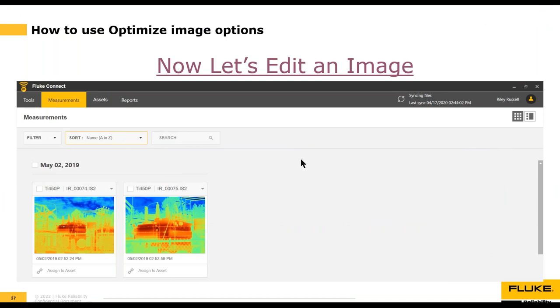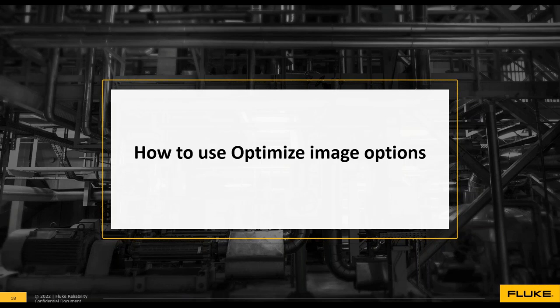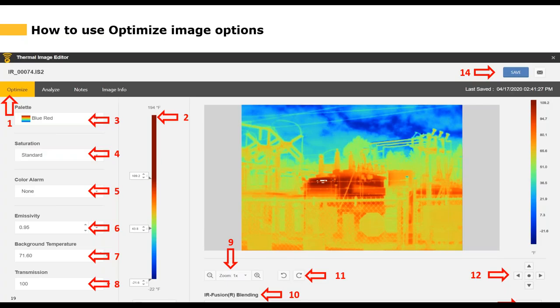Next we're going to talk about how to optimize an image, covering each option available. You use the Optimize features to make the image the best-looking image possible and highlight the area you want your viewer to focus on. In the center of the screen we have what's known as the scale, or Level and Span. The software automatically detects the hottest and coldest points in the image — known as the Span — and the midpoint, known as the Level. It then applies a color palette across that span.